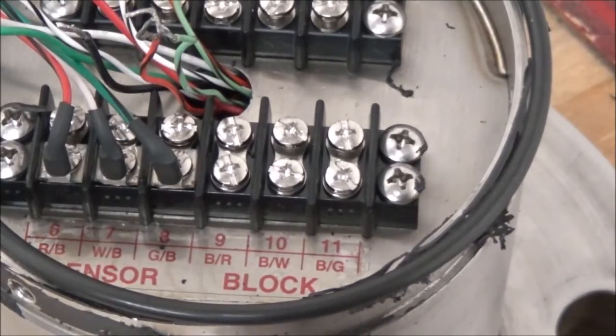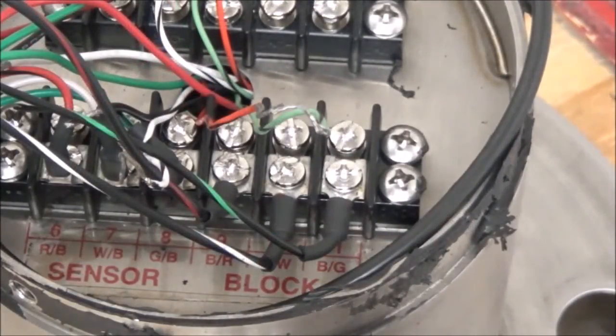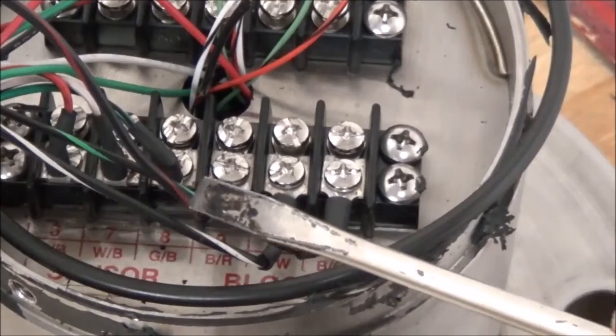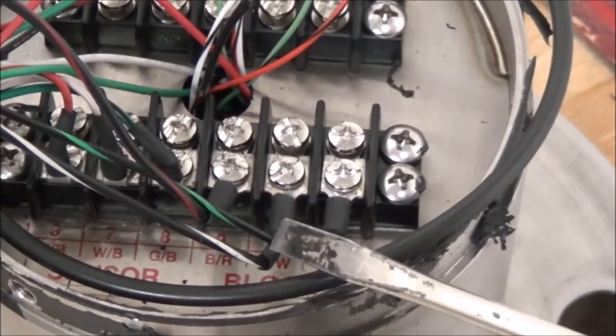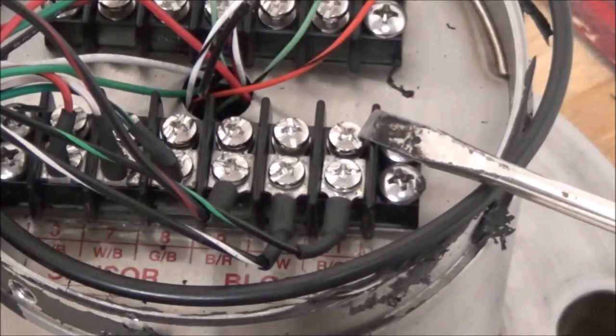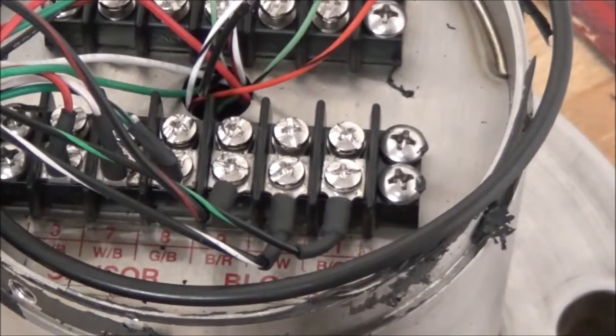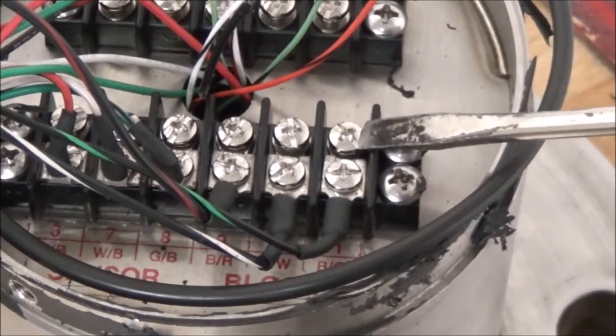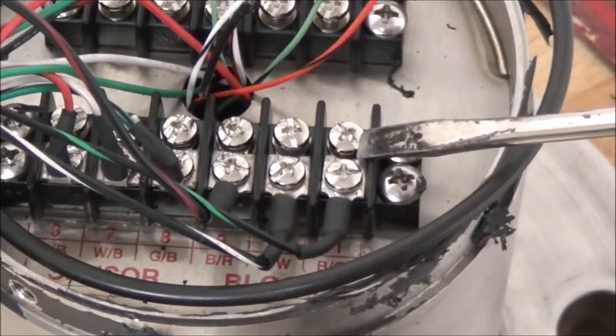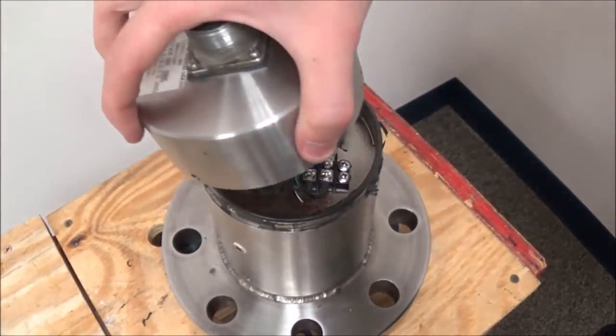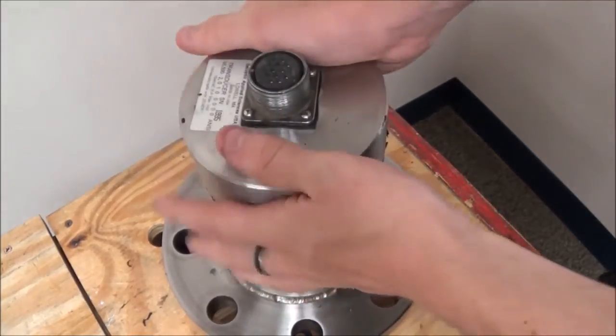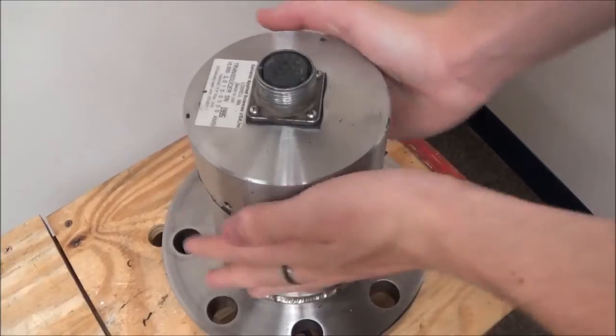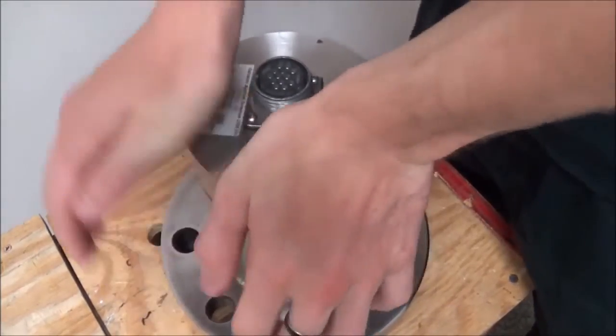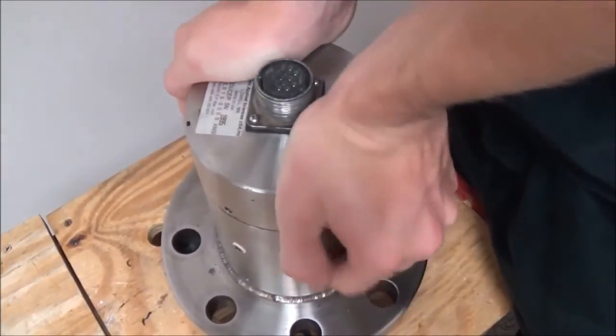The bottom of the adapter will have the last 3 remaining wires you need to complete the terminal block. And after adding these last 3 leads onto the terminal block, you are now ready to connect the block RTD into the circuit. The primary RTD's colors are red with a black stripe, green with a black stripe, and white with a black stripe, while the block RTD's colors are black with a red stripe, black with a green stripe, and black with a white stripe. Once all wires have been connected, simply pop the transducer cover back onto the viscometer for final assembly.